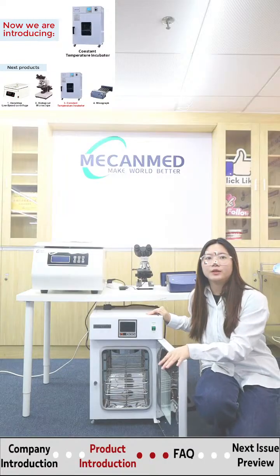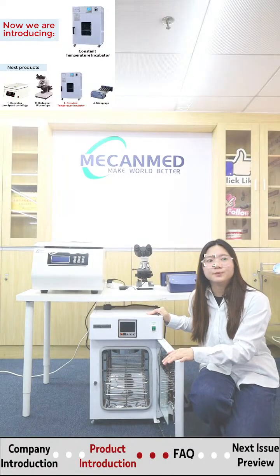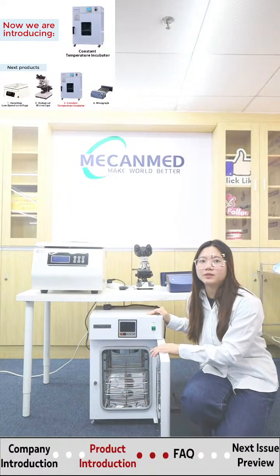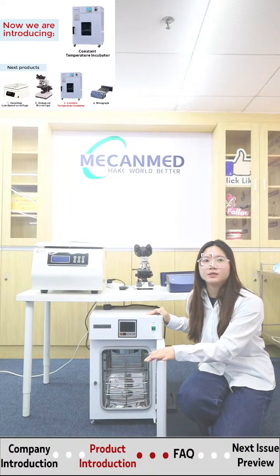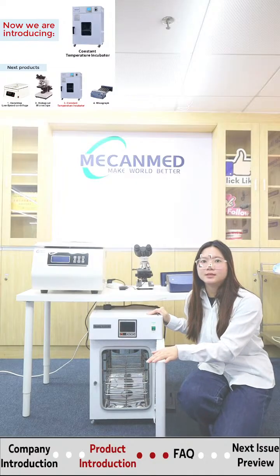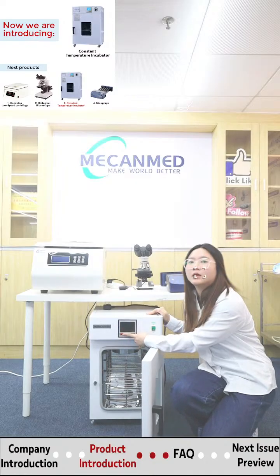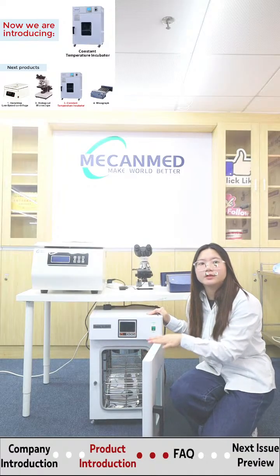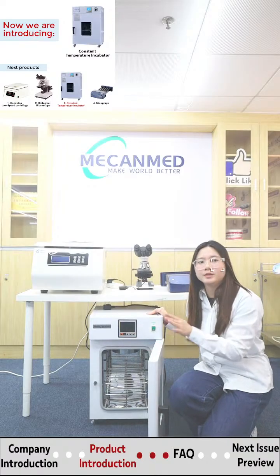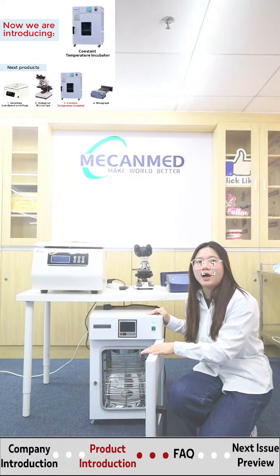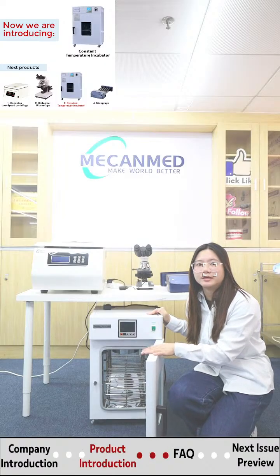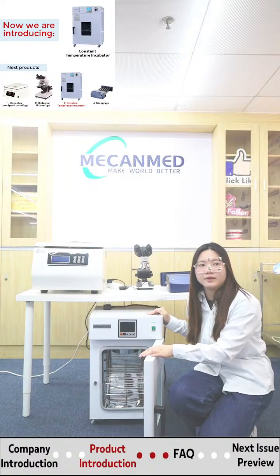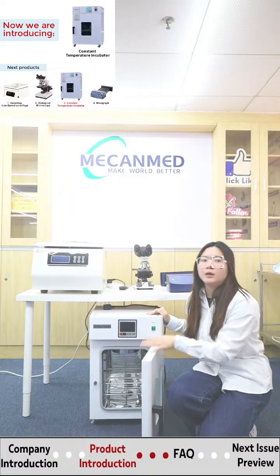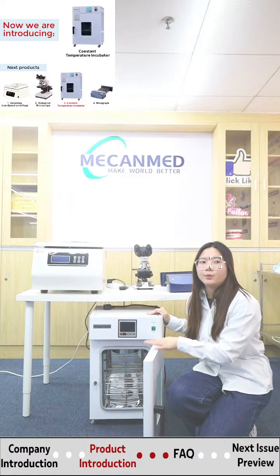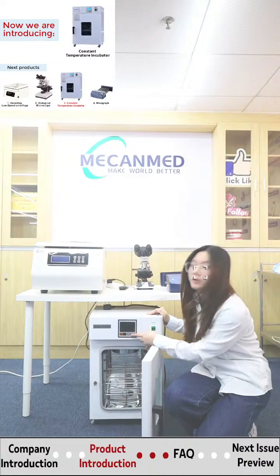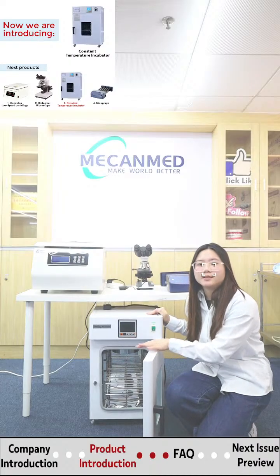Alright, let's do a quick run through of how to use this incubator. First, connect the incubator to the power supply with the power cord and press the power switch. Next, press the set button to enter the temperature setting state. The PV means the process value, which refers to the current actual temperature. The SV means the set temperature, which refers to the temperature you set. Press the up and down button to modify the set value.